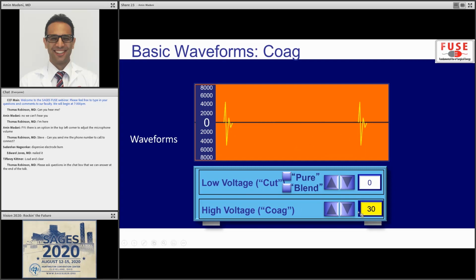But remember, you told your ESU to put it at 30 watts — 30 joules of energy per unit time delivered through the circuit. By telling it to activate only in small intermittent bursts, all that energy becomes concentrated. So that's the difference between cut and coag: coag activates only in small intervals of time, but at higher voltage, because all that energy is concentrated there.